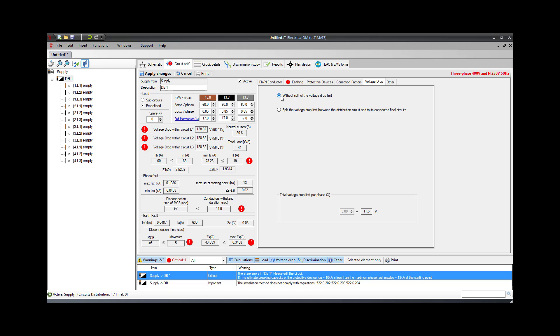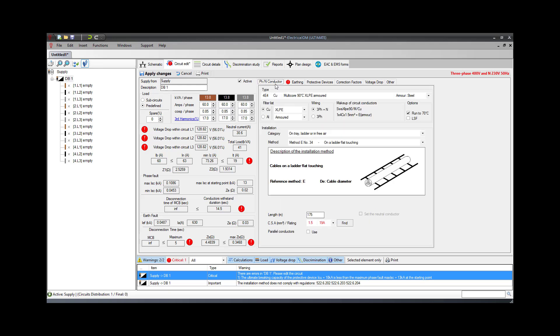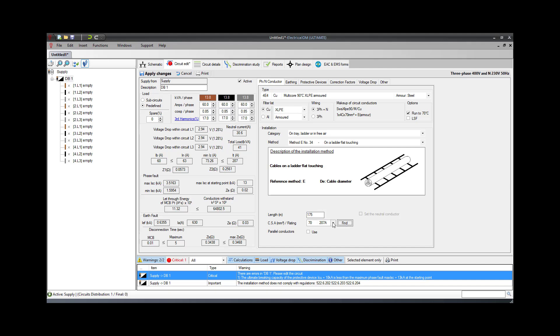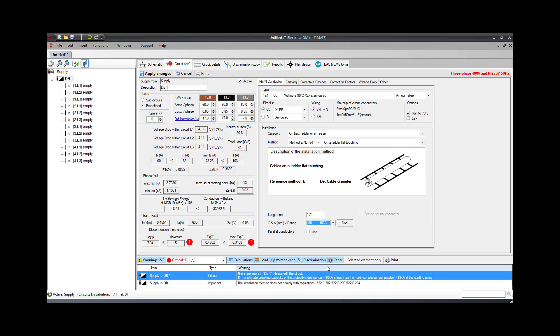At this point, we can calculate the required cable size by going back to the Phase and Neutral Conductor tab and pressing the Find button that can be found next to the cross-sectional area selection. This will select the minimum cable size required to satisfy all the calculation warnings. If we select the smaller size from the list, we can see the reason why the software has selected the particular cable size. In our example, the protective device is causing the maximum earth fault loop impedance check to fail for cable sizes smaller than 70 square millimeters.